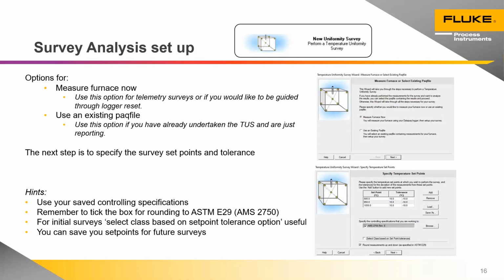In addition, if this furnace is regularly surveyed at the same set points, you can see there's a load and save as button on the right-hand side. This information is only ever entered once. You can save it in the software so you can recall it in the future. So for repetitive surveys every 3 months, you don't have to enter all the data again, simply recall it and use it. And that's where the real benefit of this software comes.